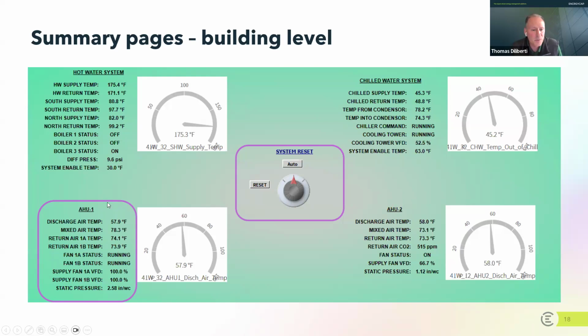Another thing I wanted to point out, in this purple bubble, is the supply fan. Whenever you have VFDs, variable frequency drives, which are motors that can spin at different speeds, they're designed to not necessarily run at 100%, and that's the point. When motors run at less than 100%, they save a lot of energy. For both of these VFDs to be running at 100% is a little bit suspicious based on the time of day I did this analysis. Also, the static pressure being 2.6 is very high for many systems. So there's a lot to unpack here. If I was an energy manager in this environment, I would spend some time understanding this unit and these systems and finding out what's going on, because it doesn't feel right to me. That's really what I'm trying to do through this whole webinar: help you understand when things aren't right so you can spend more time looking at them.